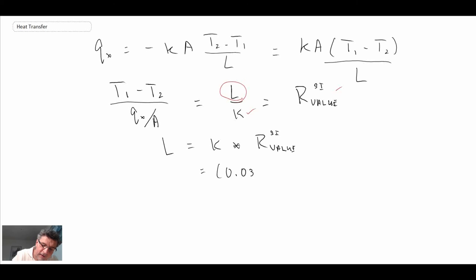So we said the thermal conductivity for fiberglass pink was 0.038, that's an approximation. 2.817 was the R-value. When we calculate we then get 0.1071 and that's in meters.